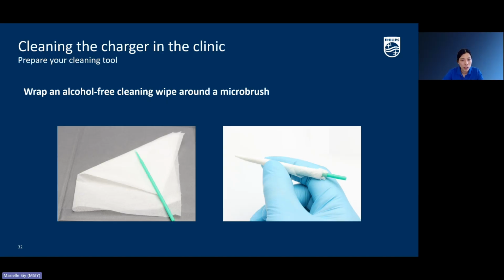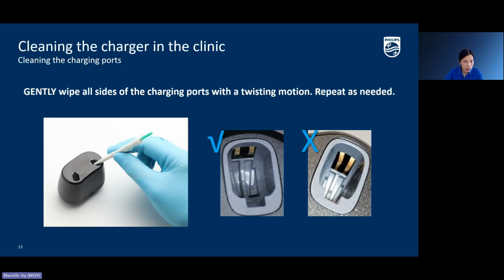After you wrap this alcohol-free cleaning wipe around the micro brush, it looks something like this. Make sure you don't use alcohol wipes, and do not use anything metal, as that will also damage the charger. Then you gently wipe all sides of the charging ports with a twisting motion and repeat as needed. You just insert it in each charging port and do this gentle twisting motion. Do not press hard, especially when you see the golden contacts, because these golden springs can easily be damaged or distorted if you don't do it right. I tried to do it. It's actually not so easy, so keep that in mind.